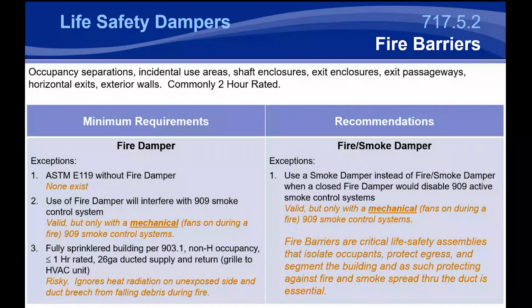One such exception is ASTM E119 without a fire damper. So if you're able to test a fire barrier that has a hole in it for a duct and there's no fire damper in there, there could be some other type of protection. There could be some other type of device that's actually stopping fire from spreading from one side of the barrier to the other. Then by all means, you can remove the fire damper requirement in that fire barrier. That's typically not common. There are going to be some other development options available, but typically this is something to be able to run a fire test. If you can run a fire test with an opening that fire won't get through with some device, by all means, remove the fire damper.